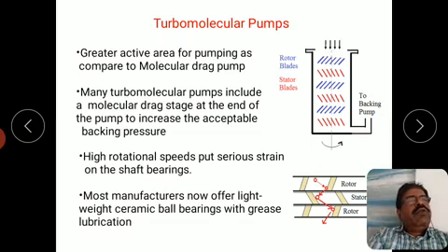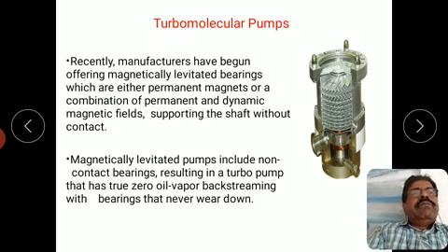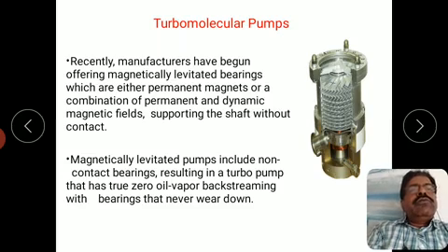But whenever lubricant comes into the picture, there is a possibility, as we have seen, of backstreaming. So these molecules of the grease or oil, whatever the lubricant used, can backstream into the chamber, and so this is the main threat here.